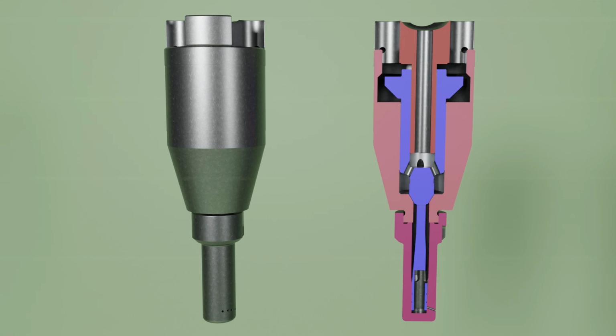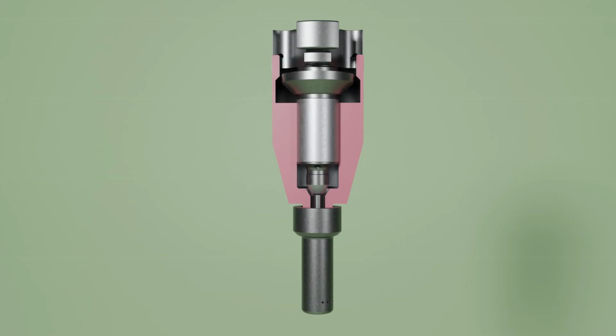It should be noted that all the components of the spindle guide are machined to close tolerances and matched with each other, hence the spindle guide needs to be replaced as a whole, and individual parts cannot be interchanged. The thrust piece is pressed into the spindle guide with an interference fit. Cutoff shaft is free to move between the spindle guide seat and thrust piece. Free movement of cutoff shaft must be checked after assembly by shaking the spindle guide and listening for the sound.